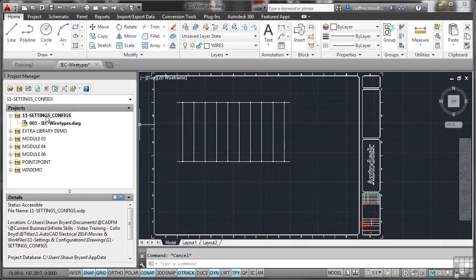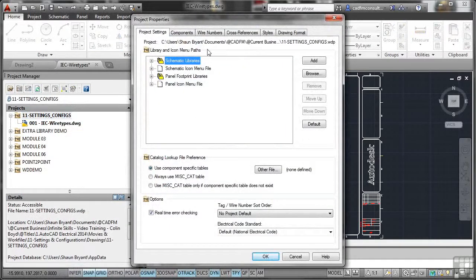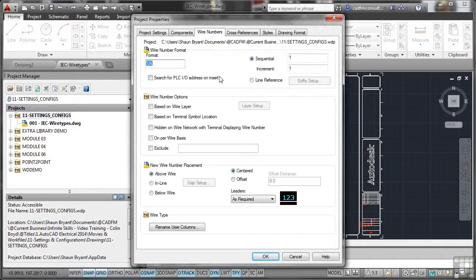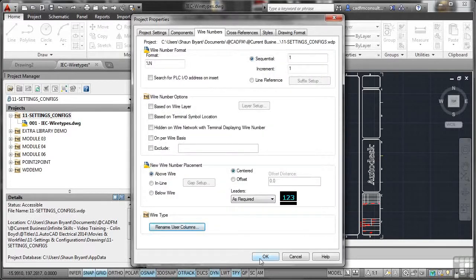Go to your project, select it, right-click and go to properties on the shortcut menu, then go to the wire numbers tab at the top of the dialog box. Wire numbering, sequential, increment — none of that we're going to change, that can all stay as is. I want to put two new user columns, so click on rename user columns. We're going to put in 'type' for user 1, and user 2 will be 'part number.' In the UK we'd write part number; in the US you might put a hash — it's just a user-defined column title, it's up to you. I'll leave the hash in there for now.